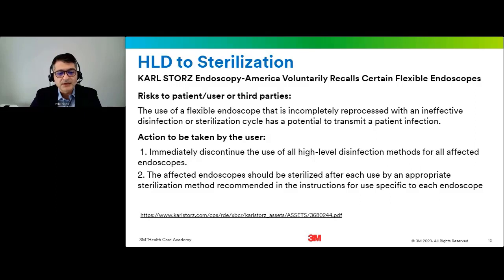In April 2022, last year actually, a flexible endoscope company was the first to issue a voluntary recall on its flexible endoscopes. The risk is the potential to transmit a patient infection, and they removed the high-level disinfection method, as well as the liquid chemical sterilization method, from their instructions for use. They mentioned that the affected endoscopes should be sterilized after each use by an appropriate sterilization method recommended in the instructions for use specific to that scope. So I want to highlight again: follow the manufacturer's instructions for use.